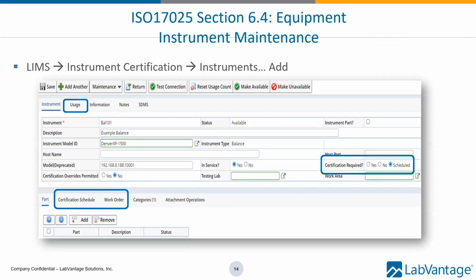In this image, we see an example of a balance that's specifically identified as BAL101 in the top left. We see that the model is a Denver XP 1500 and the type of instrument is balance, but specifically the unique identifier is BAL101. We can see that it is in service, and for the certification required there on the right, it's under a scheduled event so that when it's time, a work order will be generated and the balance would go through its appropriate verification.